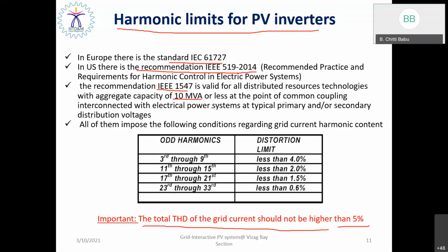So in most cases for our research purposes, we highly recommend the IEEE 519 draft 2014 standard. It was revised during 2014. This IEEE 519 was formulated by an industrial specialist group of IEEE in 1991, and then revised in 2014 as renewable energies were emerging. So please remember that the THD of the grid current should be less than 5%. Accordingly, your control algorithm has to be implemented.